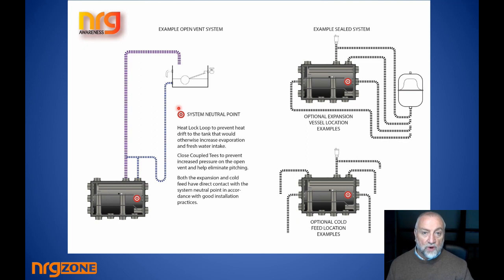There's a simple trick to show and prove how well your cold feed and expansion is. You scoop some water from the heating tank into a clear vessel like a glass or a jar, and you immerse the outlet of the vent pipe into the water, and then you get someone to turn on whatever pumps could be turned on in the system, and after a while turn them off, and you observe the level of water in the glass. If the water pushes into the glass, you've got air moving up the expansion, which is a problem. If the water pulls out of the glass, you've got a problem as well. There's something wrong with your neutral point and where you're connecting your cold feed and expansion to.